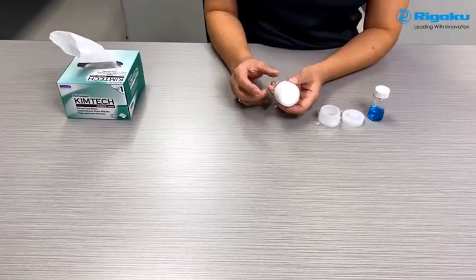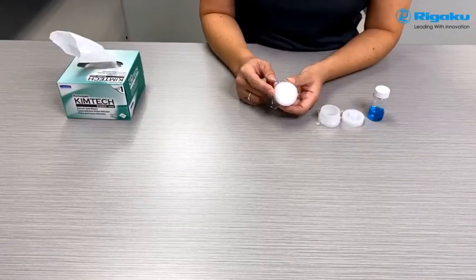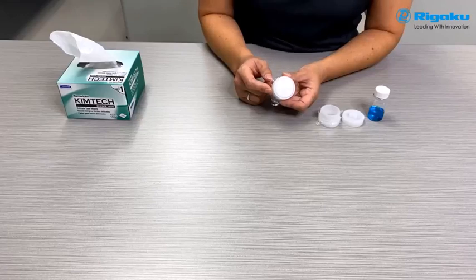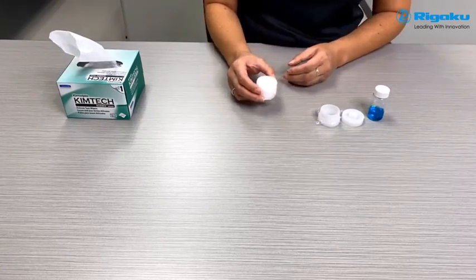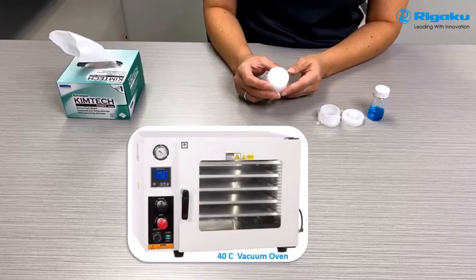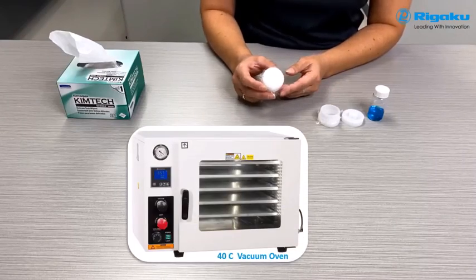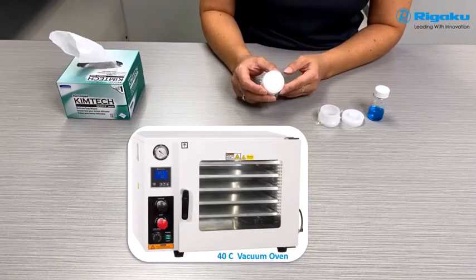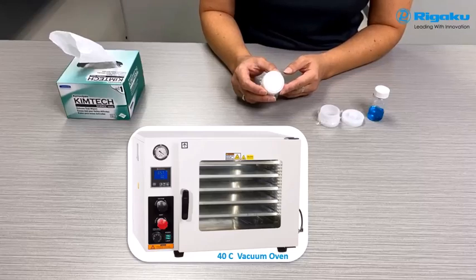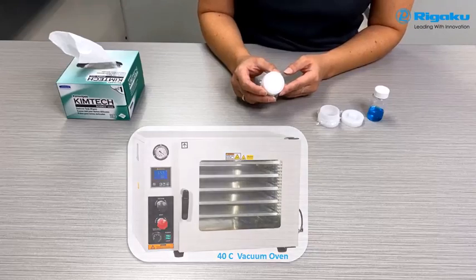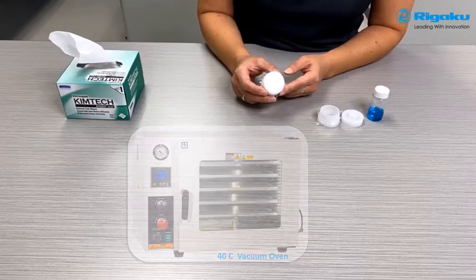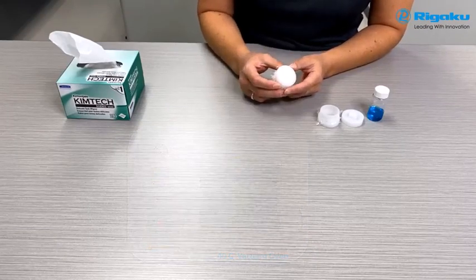Okay, so once you've determined the choice of film that you want to use, we recommend that you test it offline first before you expose it to X-rays. For a powder sample, I like to put it in a vacuum oven at say 40 degrees C. Maybe there's something that's going to off gas from the sample. I'm going to test that first in a vacuum oven at about the temperature it's going to see on the machine. And if it's good there for 5 minutes, it's good to go for all the samples that are like that.